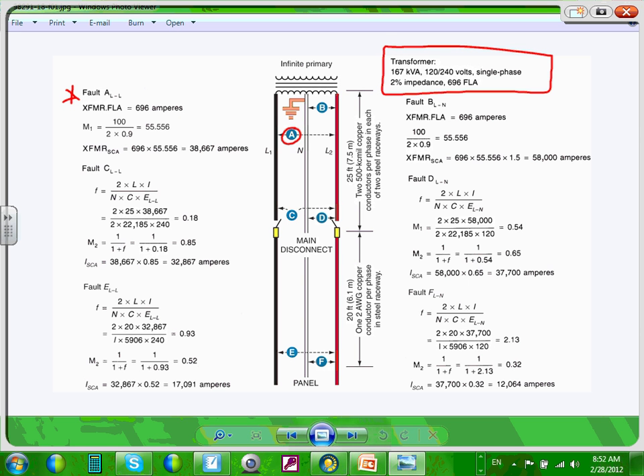The first thing you usually do is find the full load current, which is I full load current equals 167K divided by 240, and this should give you 696 amps, right? Should give me 696 amps. Can anybody try that one? If you take 167 divided by 240, you should come up with 695.8, which is 696. Any question about step number one?